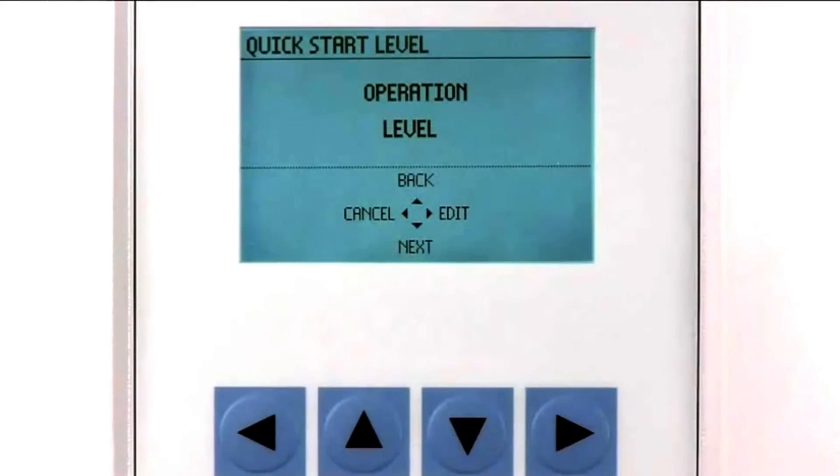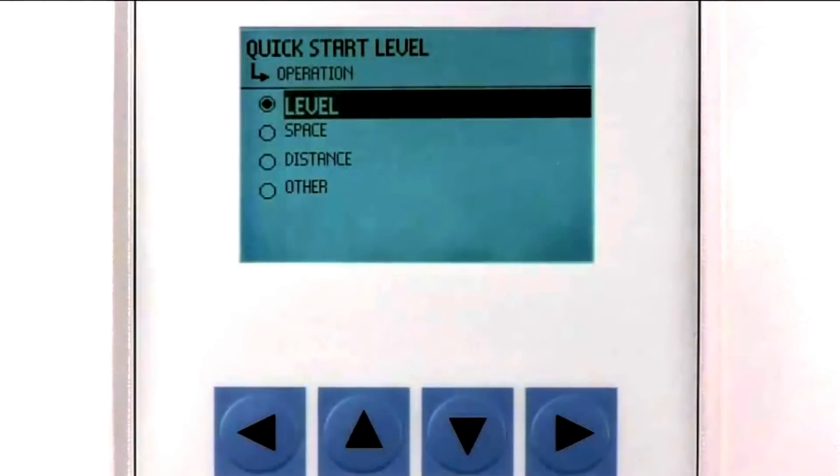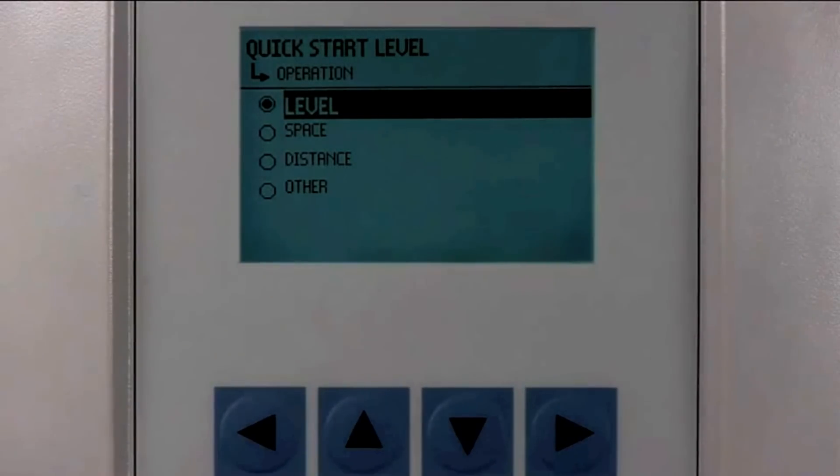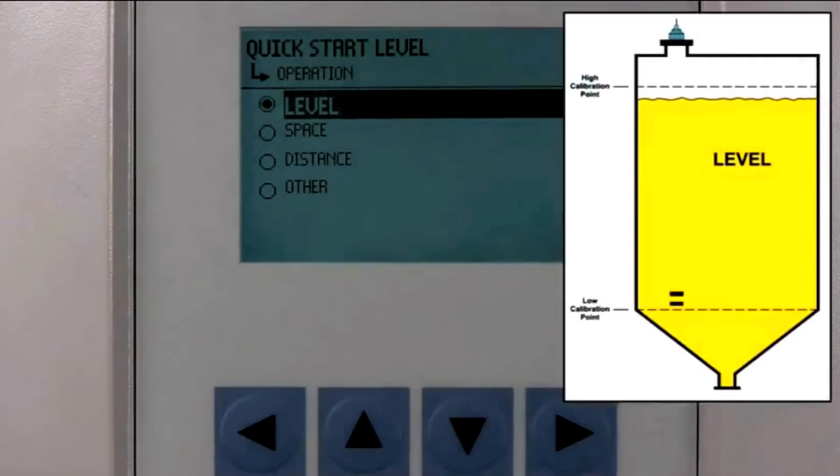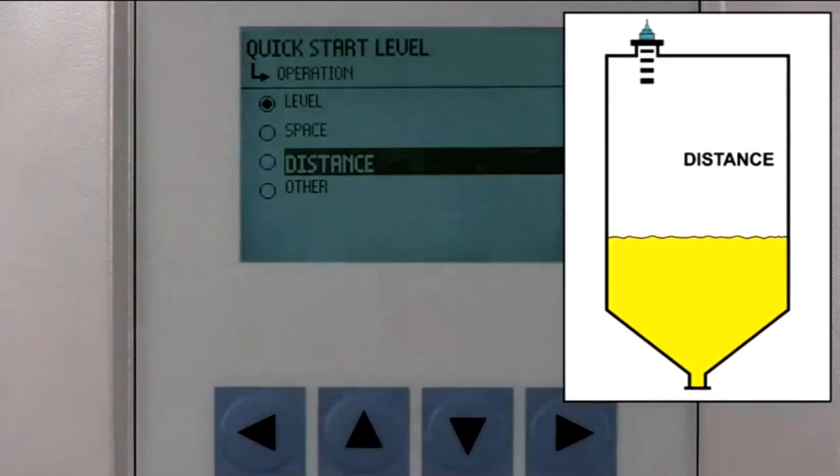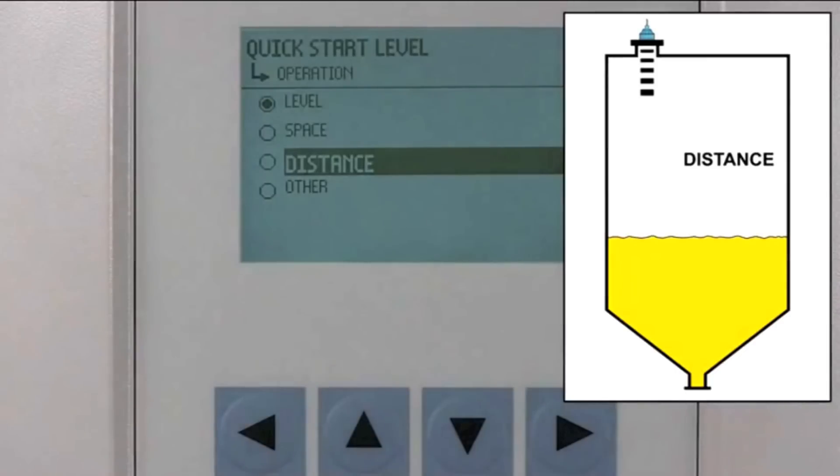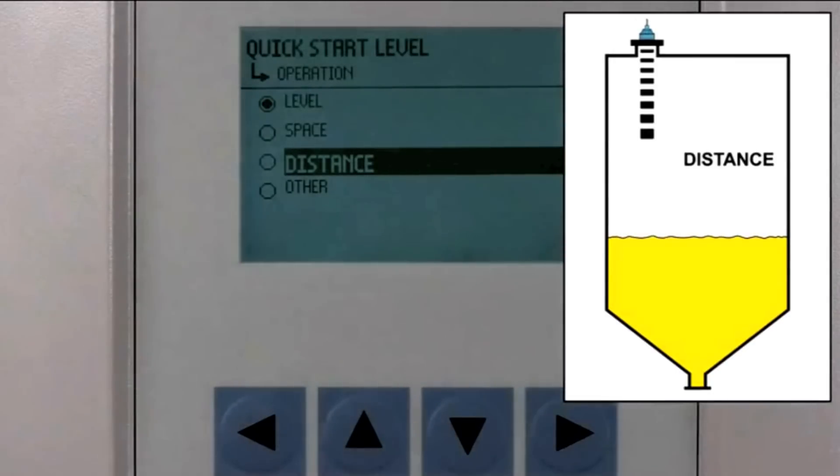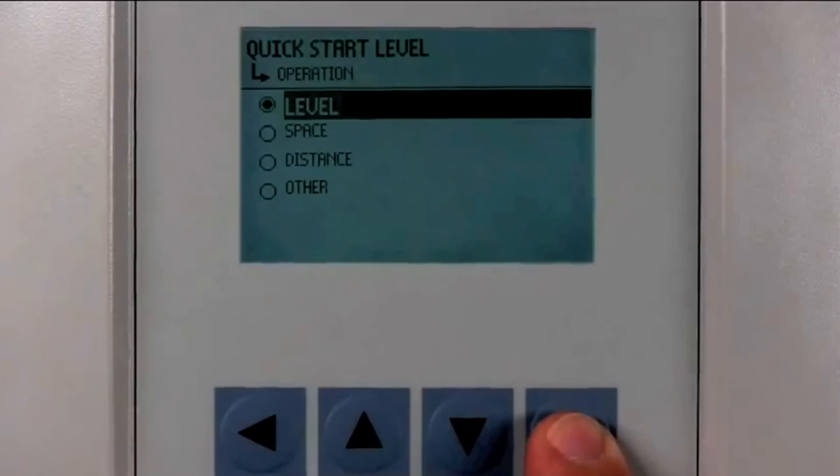The Operation parameter defines the measurement mode used to calculate the displayed value and the corresponding milliamp output. There are three choices for this parameter: level, space, or distance. The level mode measures the height of the material in the vessel from the low calibration point to the high calibration point. The Space mode measures the distance from the high calibration point to the material surface. The Distance mode measures the distance from the transducer face to the material surface. In our application, we will select the level mode.